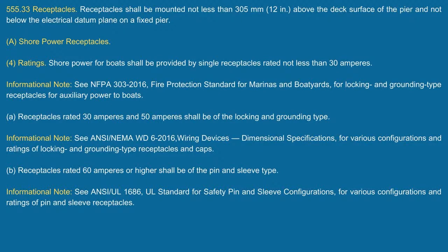You know what amazes me about this? If I'm plugging into that receptacle, why are they so specific saying all my other receptacles have to have Class A GFCI protection, but when I go to the receptacle for shore power, it doesn't? But yet I'm going to allow to have my GFPE protection at the equipment or the feeder upstream.